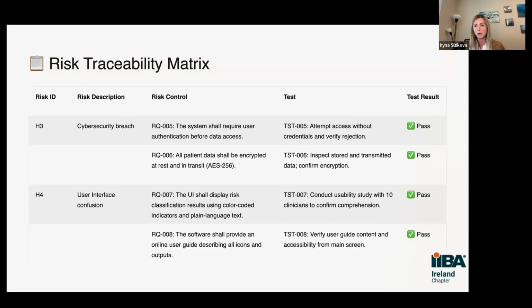Let's look at one more due to time restrictions and then proceed to the next topic. For example, user interface confusion. The UI shall display risk classification results using a color-coded indicator and plain language text. To cover it with a test case, we conduct a usability study with 10 clinicians. We defined a number of clinicians and confirm comprehension. If all of them understand how to follow the scenario, we say that this case is successful. Depending on the result, we decide if further mitigation is required. Then next, risk mitigation number 8: the software shall provide an online user guide describing all icons and outputs. During the test, we verify the user guide content and accessibility from the main screen.